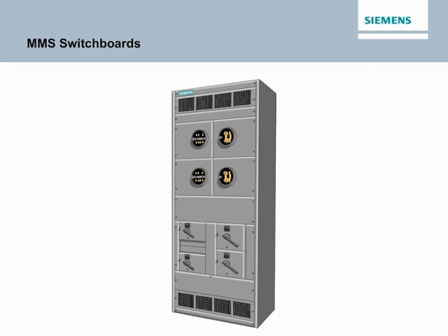MMS switchboards have the following additional features: hot sequence metering standard, cold sequence optional, 50,000 amp symmetrical bracing standard, higher bracing is available. All meter sockets are pre-wired, for 100, 200, or 320 amp sockets. Copper or aluminum buses available. Units are front accessible. Type NEMA 1 or NEMA 3R enclosure.